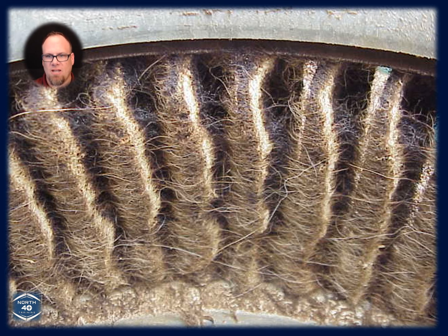And so the technical advisor gets involved, goes out there. First thing that he looks at is the surroundings, right? What's around that coil? What's around that condenser that could affect the way it operates? This is just a different mindset. Some people don't think that way, but the problem isn't always with the mechanical appliance that is showing the problem. Sometimes the problem is with the surroundings. And so he begins to look at some of the surroundings. And one of the beginning things, of course, was the filter and the duct work and all of that. But then he opens up that bottom panel and looks at the blower, and the blower wheel is completely full of hair. Now look at this thing. That's pretty next level. And so at that point, obviously, the contractor was a little embarrassed.